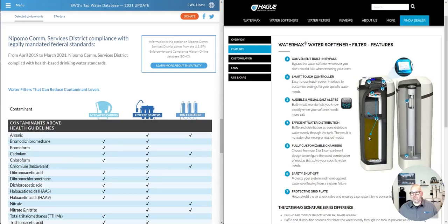Carbon works great for removing organic chemicals, but it works by adsorption. So at some point that carbon is going to run out of capacity. You then have to replace that carbon. So the beauty of this design is instead of having to replace a carbon filter, we're replacing the carbon out of this media bed here. We're actually extending the life of that carbon by removing that chlorine before it hits the carbon. Now that carbon can last much, much longer.